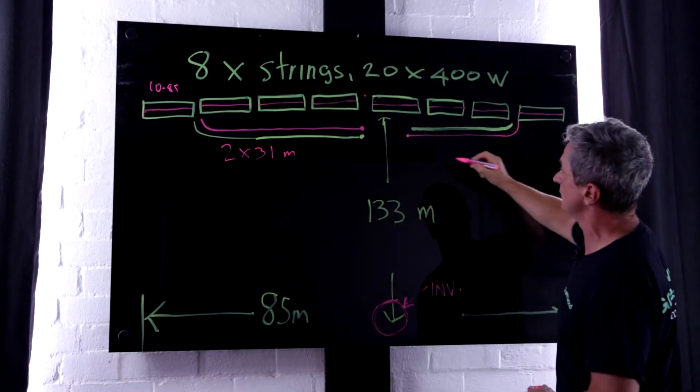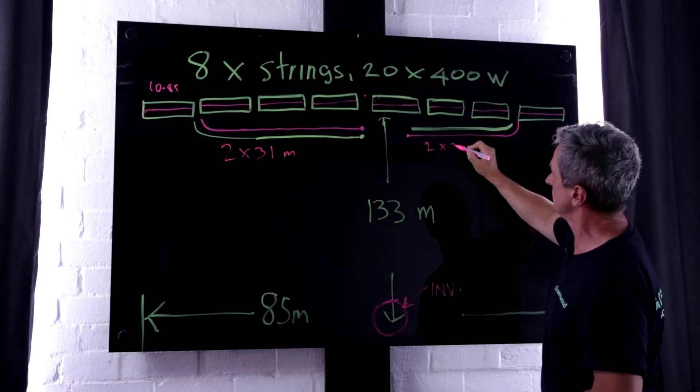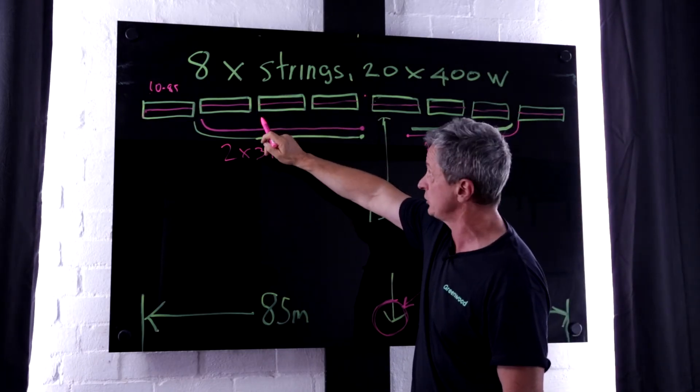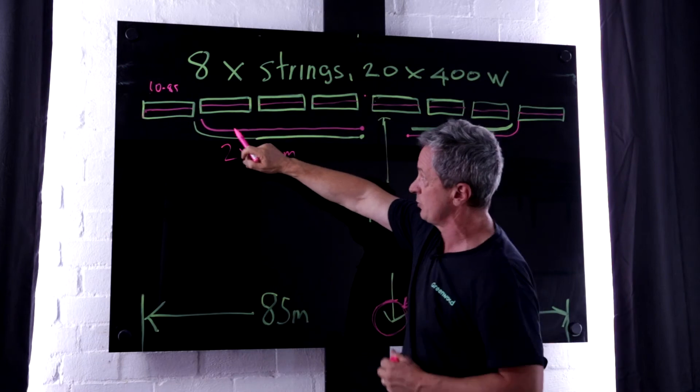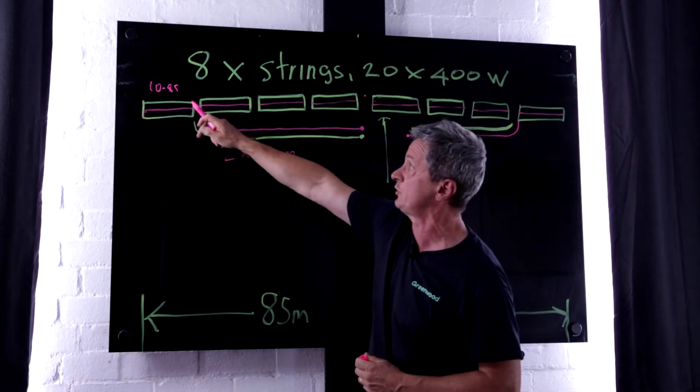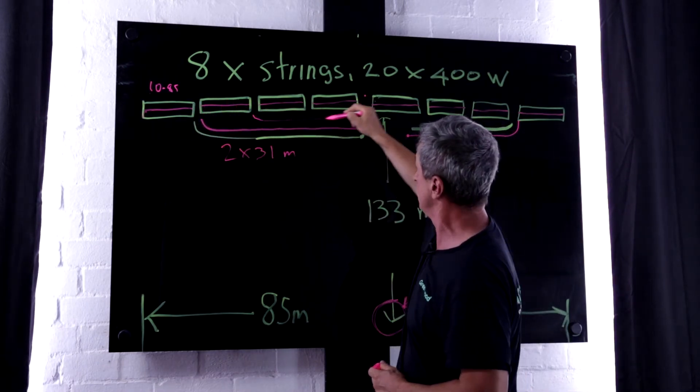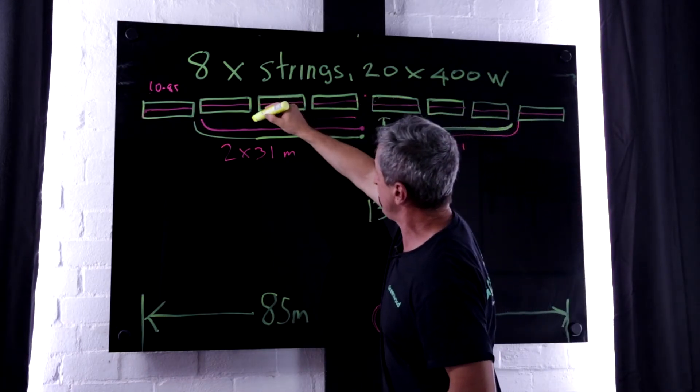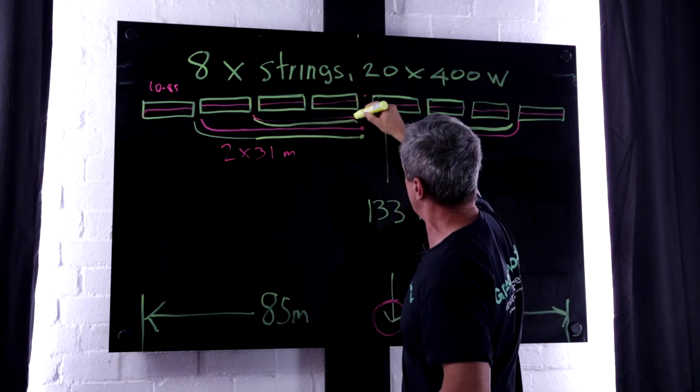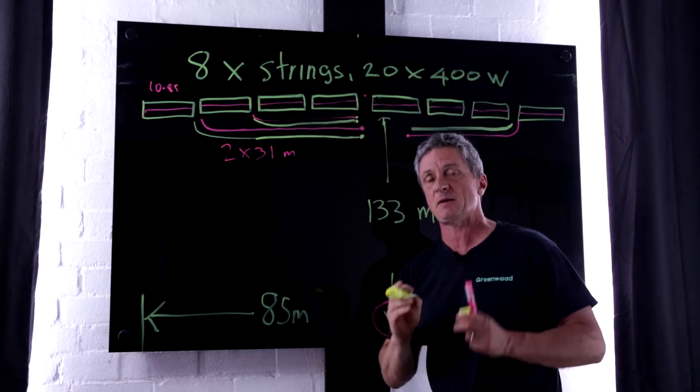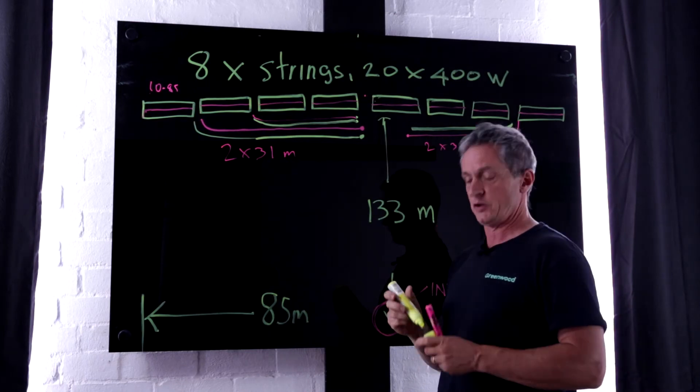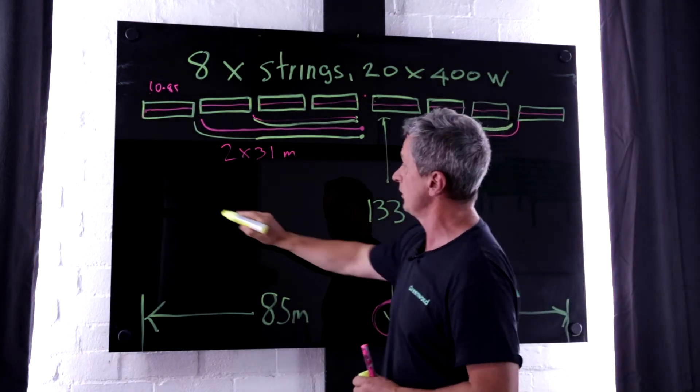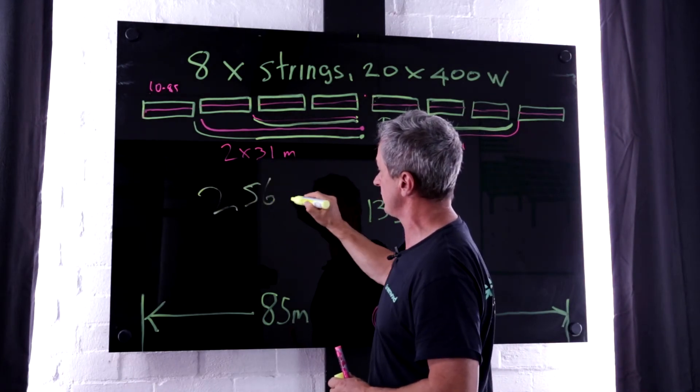And on the same side, we have here. Now obviously the next string, same consideration, that distance you remove another 10.85 or actually two times 10.85 to get to that point. So it's a fairly simple way of working out how much cable per row that you use. And in the case that we're presenting today, the total is 256 metres.